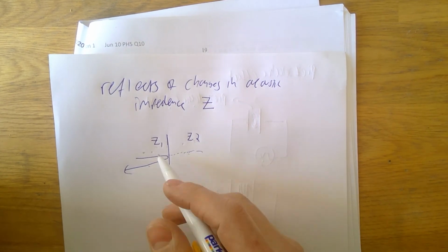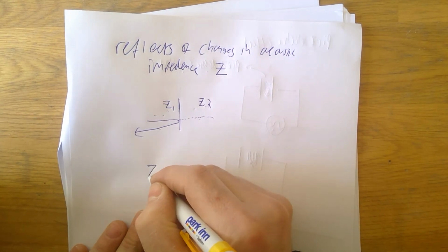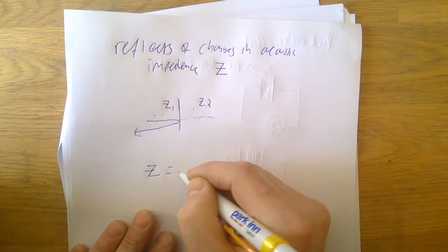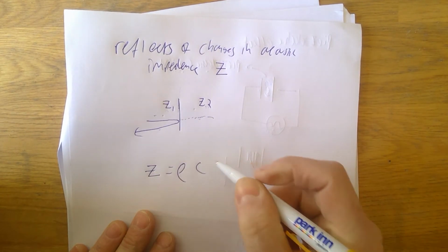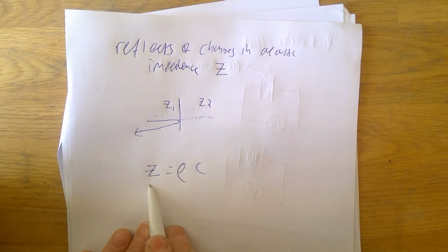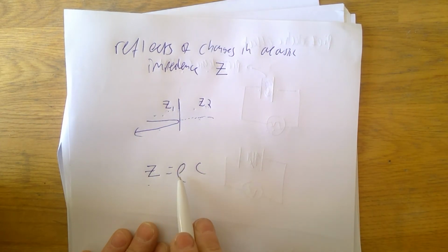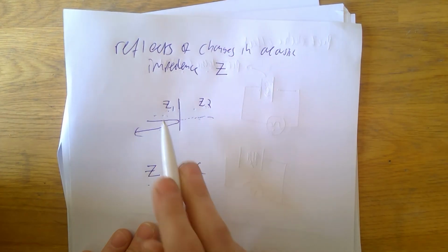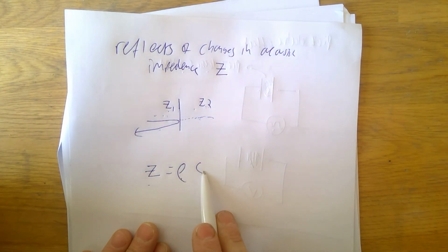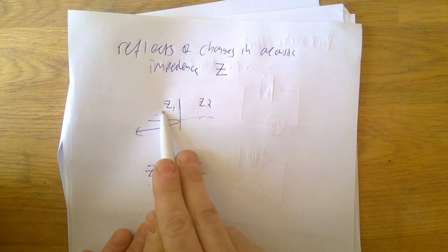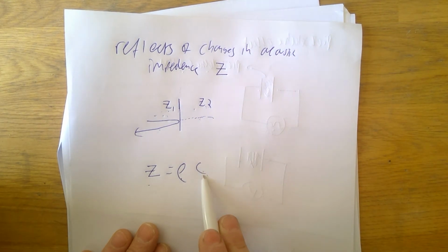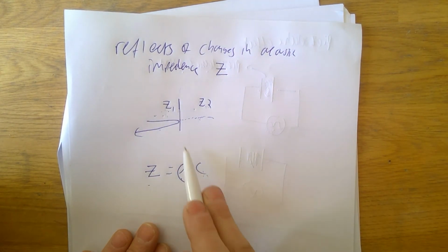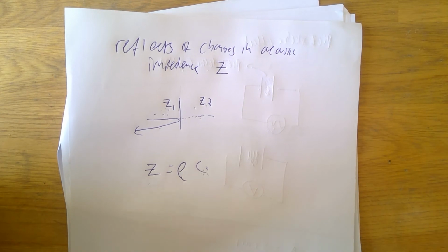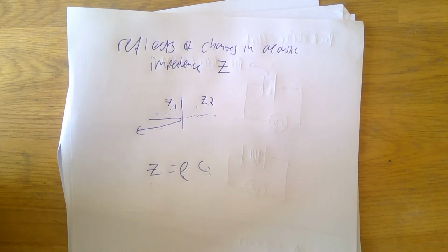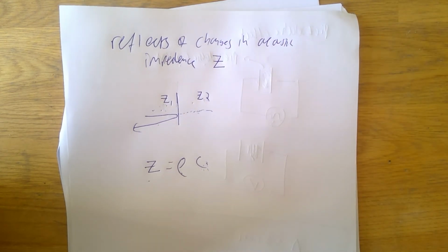How much depends on the ratio of these two values. So how do we calculate acoustic impedance? Z equals rho c. The acoustic impedance of one material equals the density of that material multiplied by the speed of ultrasound in that material. Don't use the speed of light, the speed of ultrasound in that material. And that will be different for each material as well. Now, that's the equation that's in the data book.